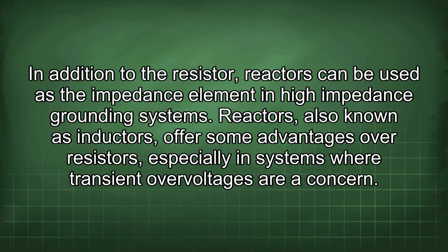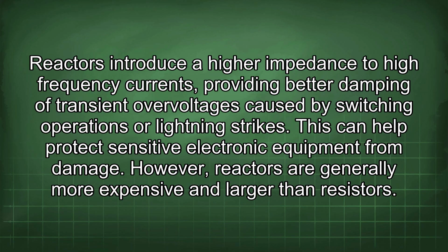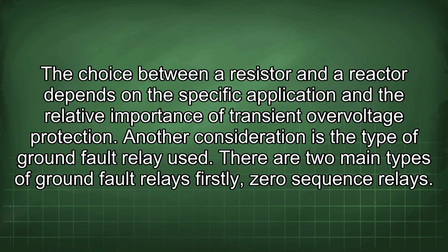In addition to the resistor, reactors can be used as the impedance element in high-impedance grounding systems. Reactors, also known as inductors, offer some advantages over resistors, especially in systems where transient overvoltages are a concern. Reactors introduce a higher impedance to high-frequency currents, providing better damping of transient overvoltages caused by switching operations or lightning strikes. This can help protect sensitive electronic equipment from damage. However, reactors are generally more expensive and larger than resistors. The choice between a resistor and a reactor depends on the specific application and the relative importance of transient overvoltage protection.